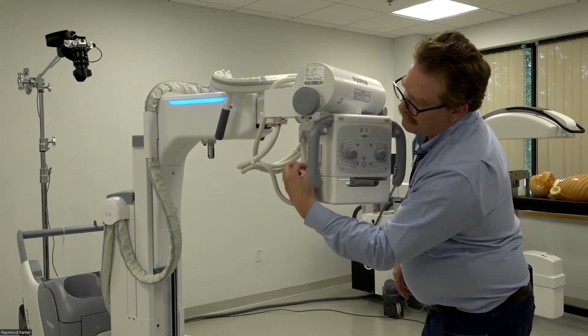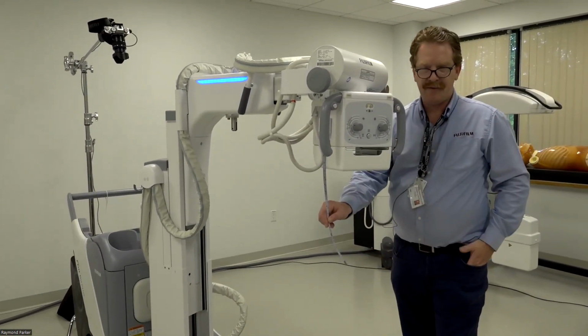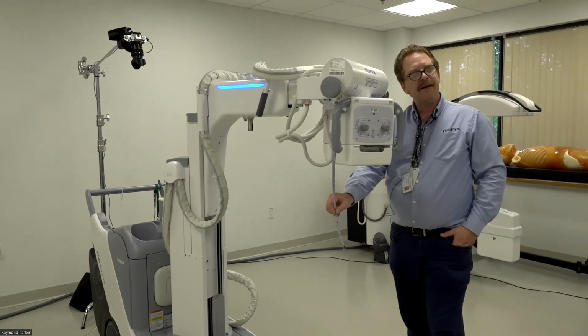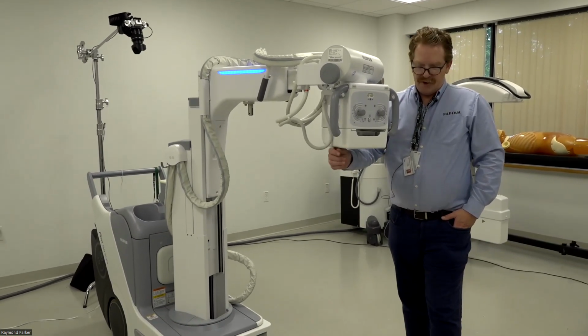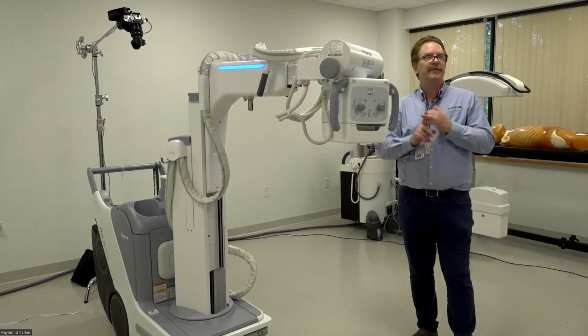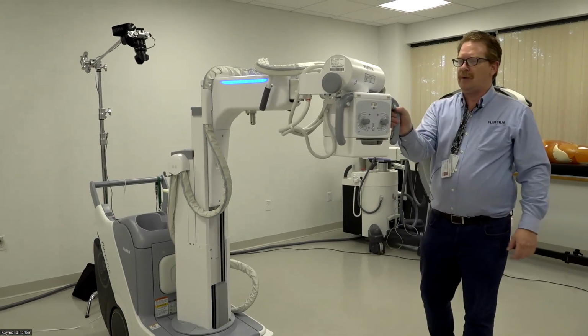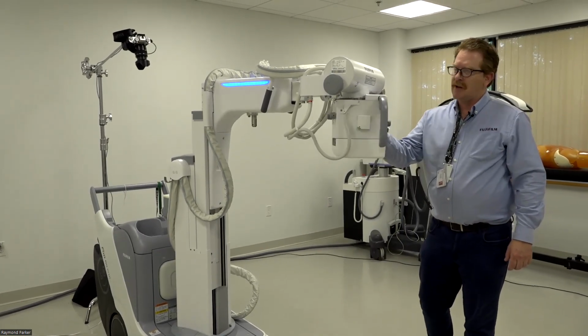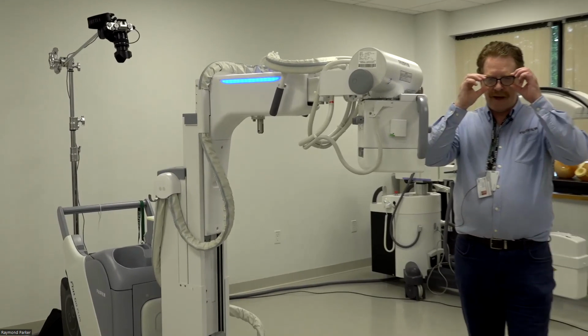Please take the time to show the technologists that there is a tape measure available for measurement of your SIDs. That should be discussed when handling your S numbers as well as your virtual grid function. Those virtual grid menus are built for specific distances, and image contrast can vary depending on the SID used.